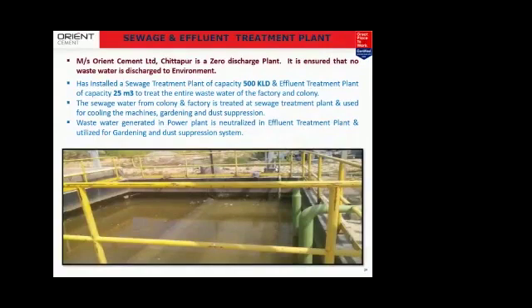This is regarding the wastewater treatment, ETP. We are a ZLD, sir. Actually, we are zero liquid discharge. We are not discharging any of the effluent outside the plant. We are totally utilizing this in cooling the ACCs, that is, the air cooled condensers. We have provided such a system that this water is treated and pumped to that system so as to cool the condensate steam, which in turn improves our vacuum in the turbine. So it is also used for that.